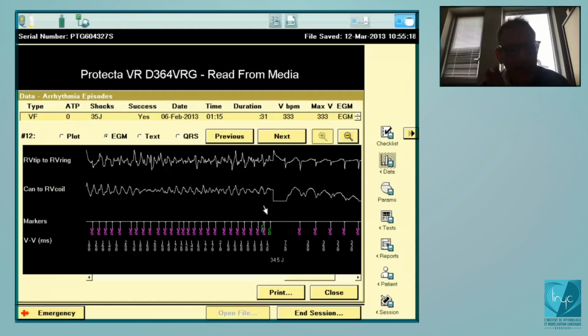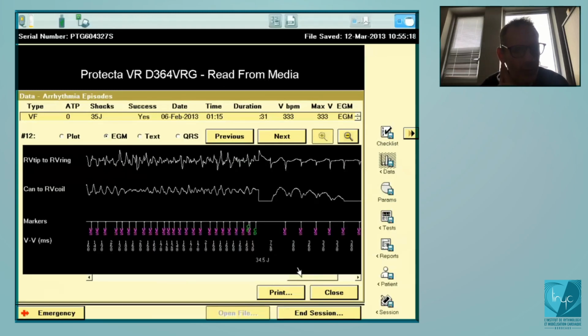It means that once you charge the capacitor, if there is a spontaneous reduction of the arrhythmia, then the shock will not be delivered. So it's non-committed. And one of the criteria is that at the end of the charge, it will analyze the next 5 cycles. And if there are at least 2 fast cycles, how you define a fast cycle, there are details, but whatever. But you see here, after the charge, there is one cycle which is labeled VS, and then the second one. And then since the first two are fast, it will deliver the shock on the second one, okay?